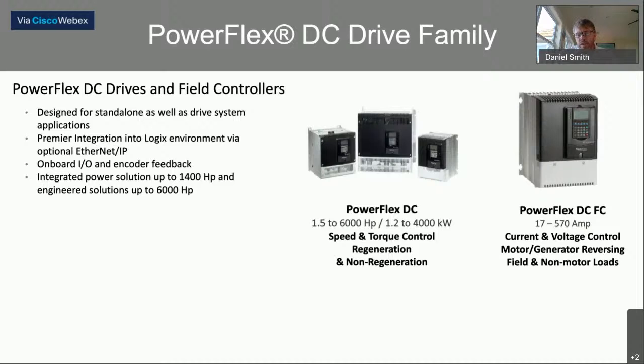This drive comes in two flavors. There's a 2-quadrant drive and a 4-quadrant drive. The 2-quadrant doesn't have regenerative capabilities, whereas a 4-quadrant drive has the ability to regen that overhauling load and put it back on the grid. Next slide.